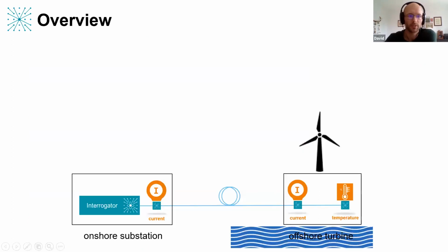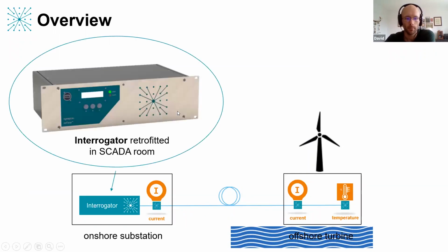To jump right in, this is a rough overview of the installation we had. On the onshore side in the substation, we installed the interrogator, which is the main measurement unit, which is doing all the processing, publishing data, and communicating with all other devices in the substation. This is connected to our sensors via a single optical cable.